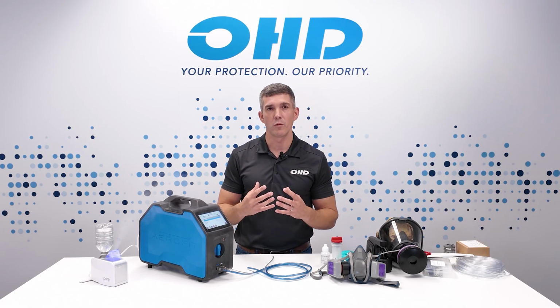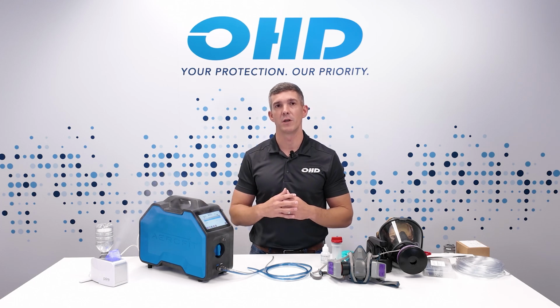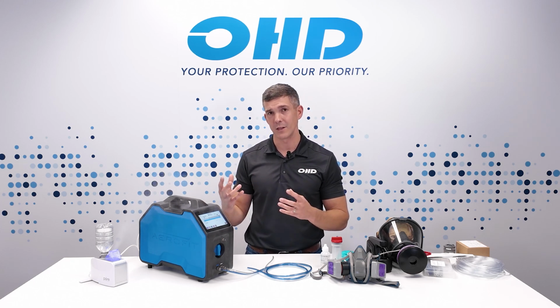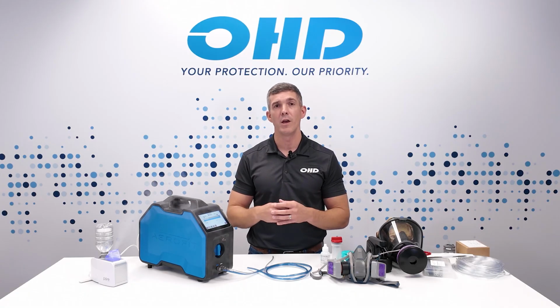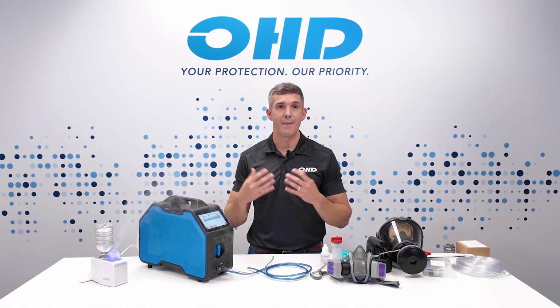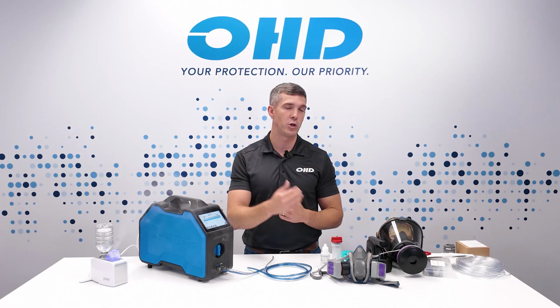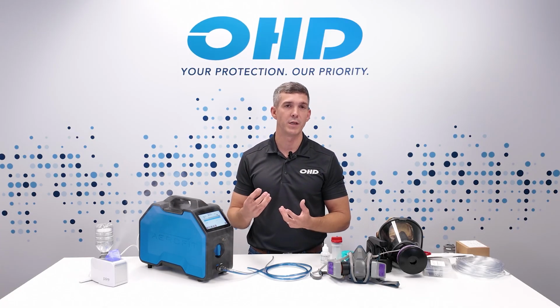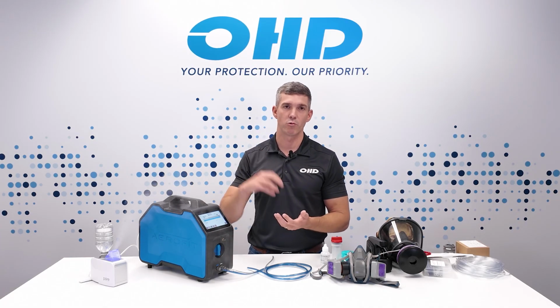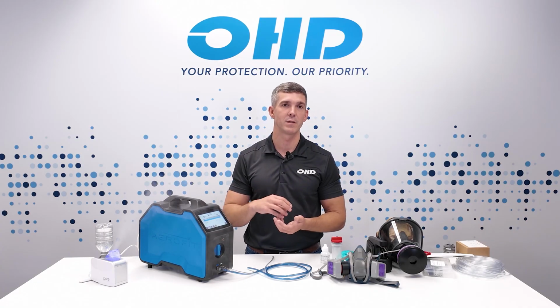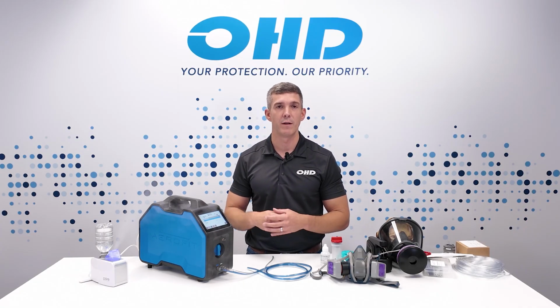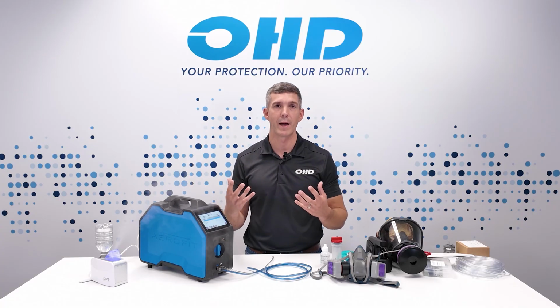Another important thing for troubleshooting is low alcohol symptoms. So again, that could be where the concentrations in the unit begin to go down. You're seeing low concentrations, and that's a sign that you have low alcohol in your wick. And again, an easy way to address that is to resaturate that wick for a number of minutes and then reinsert it into the unit and see if your concentrations climb back up.